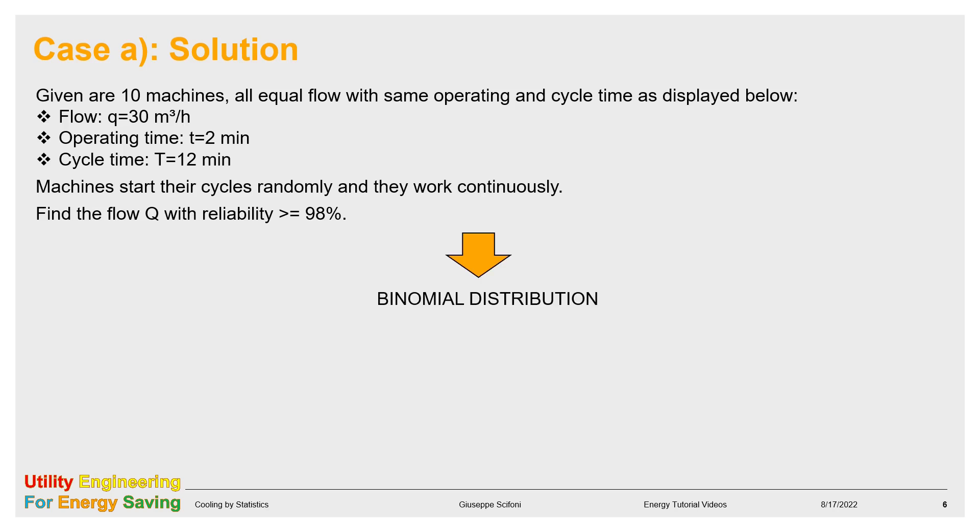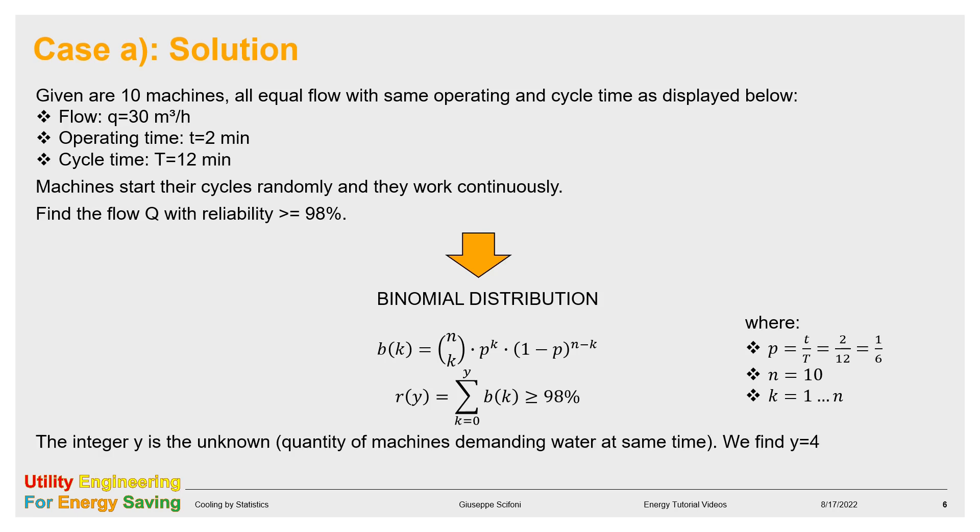The statistics describing this configuration is the binomial distribution. The probability that K machines are demanding water is given by a formula. The probability that a maximum of Y machines are demanding water is the sum of the single probability. The sum must be greater or equal to 98% as per our choice. Y is our search unknown. We find Y equal to 4 machines. Eventually, the capacity of the system is Y times Q, 120 cubic meter per hour.